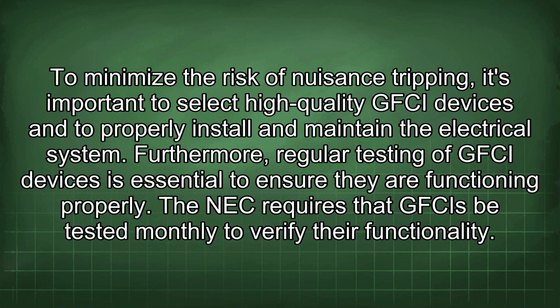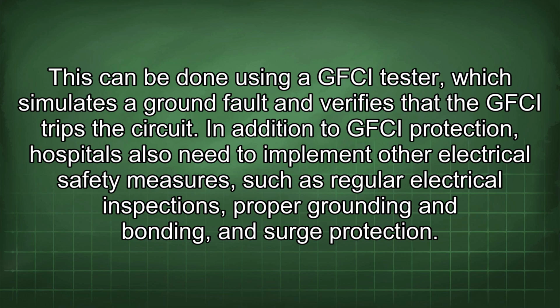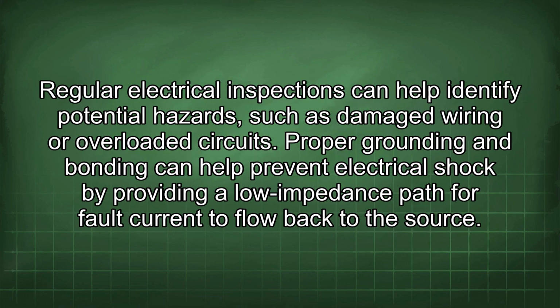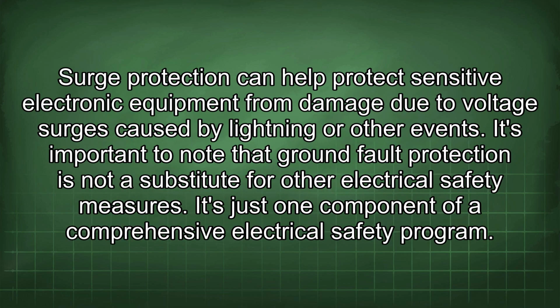The NEC requires that GFCIs be tested monthly to verify their functionality. This can be done using a GFCI tester, which simulates a ground fault and verifies that the GFCI trips the circuit. In addition to GFCI protection, hospitals also need to implement other electrical safety measures, such as regular electrical inspections, proper grounding and bonding, and surge protection. Regular electrical inspections can help identify potential hazards, such as damaged wiring or overloaded circuits. Proper grounding and bonding can help prevent electrical shock by providing a low impedance path for fault current to flow back to the source. Surge protection can help protect sensitive electronic equipment from damage due to voltage surges caused by lightning or other events.